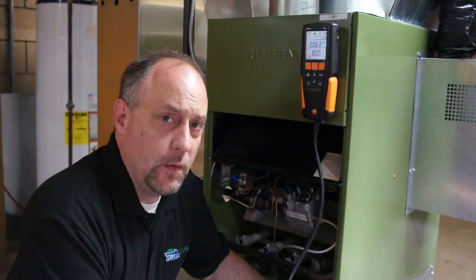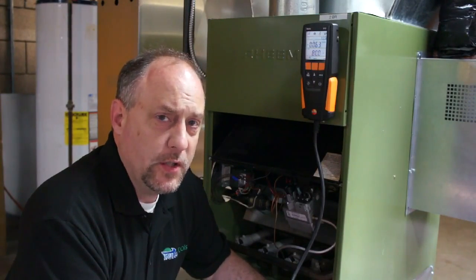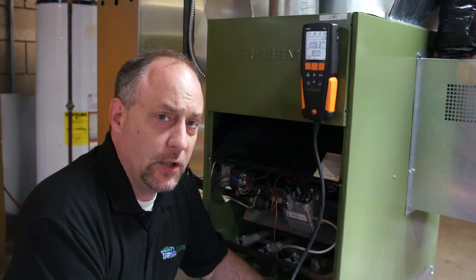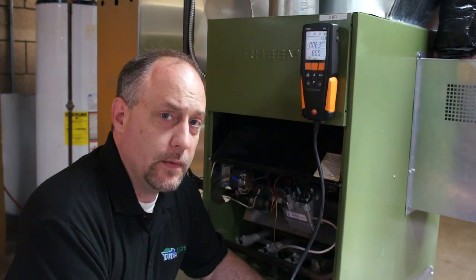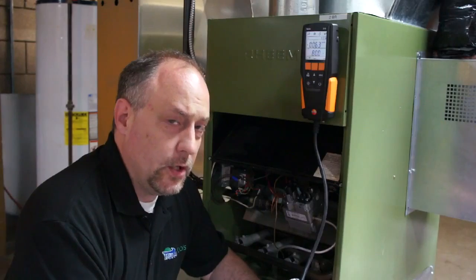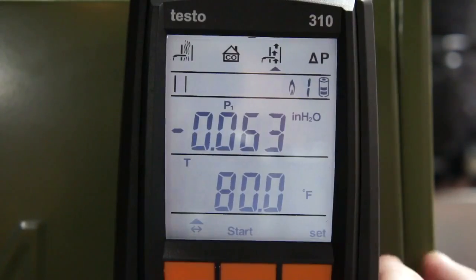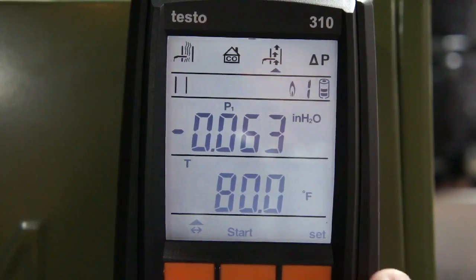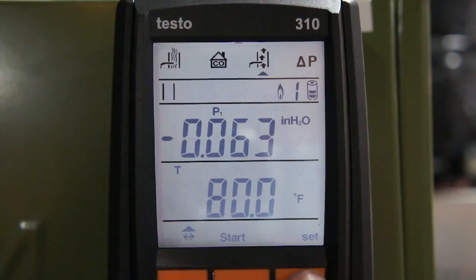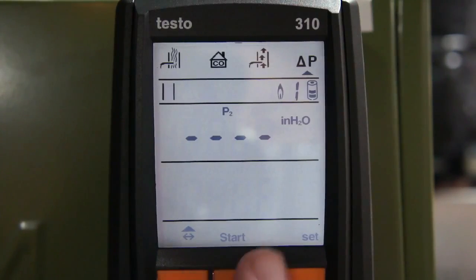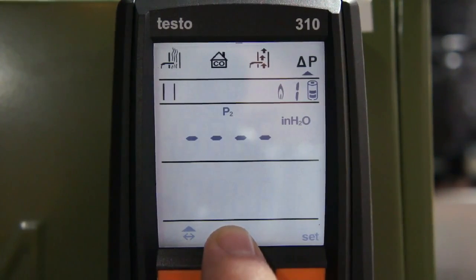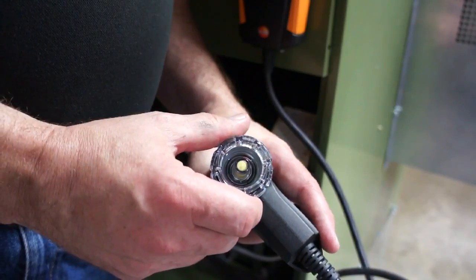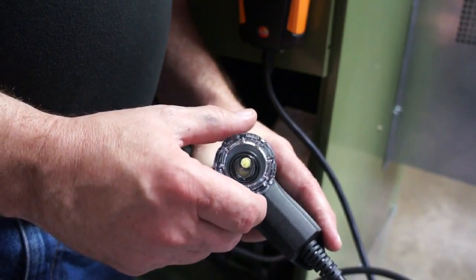Now that we've measured our ambient CO and verified adequate draft, the next thing is to check the fuel pressure on the gas furnace. The manometer built into the Testo 310 is more than adequate for doing both — it has a high-resolution range for measuring draft, but it can also read pressures up to 16 inches of water column. So we're going to configure the instrument for that. I'm going to push the left-right arrow again and you'll see it's flashing 'plug' — because what we have to do next is take the cap off the particulate filter and plug the gas path. We have to plug the gas path because we don't want natural gas to pressurize the fuel gas cells.